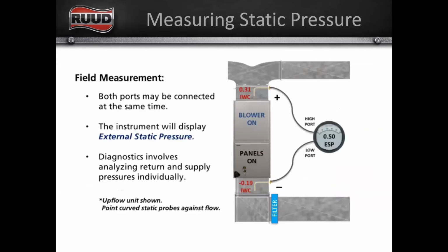All right, so field measurement here, we've got a pressure tap in our supply. We've got one in our return. You can see that they're both pointing into the flow of the air. You can see that we're checking on our return side between the filter and the air handler. We've got our positive, or our supply, hooked up to the plus on our magnehelic gauge. We have the negative, or the return, hooked up to the low port, and on some magnehelic gauges, these might read as just plus and minus.